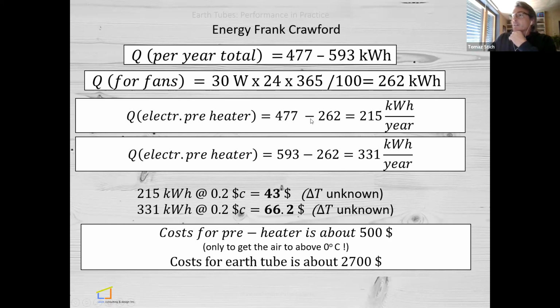So if we subtract this from the total kilowatt hours, we get 215 kilowatt hours or 331 kilowatt hours. So multiply that with 0.2 cents, we get to $43 or $66 for the whole year or the heating season. Whereas I have to say that delta T is unknown and it's only till zero, right? So you don't get 10 degrees or 12 degrees Celsius. So the cost for a preheater is about $500 built in, only to get the air to above zero. Whereas the cost for an earth tube install is about 2,700.